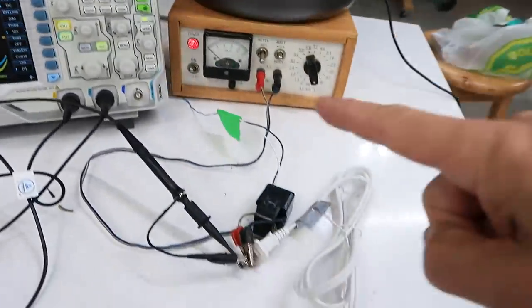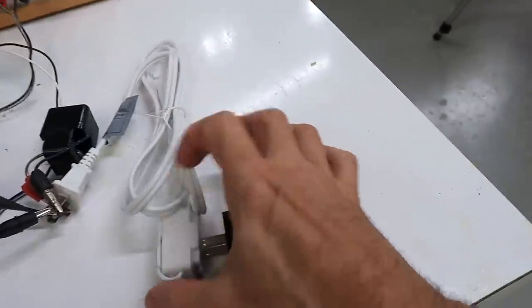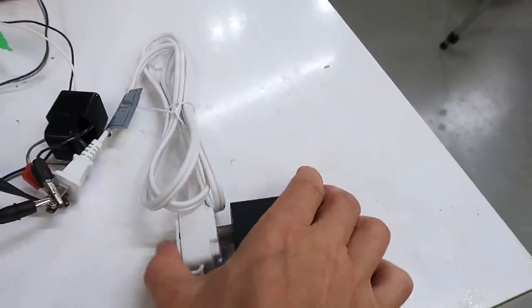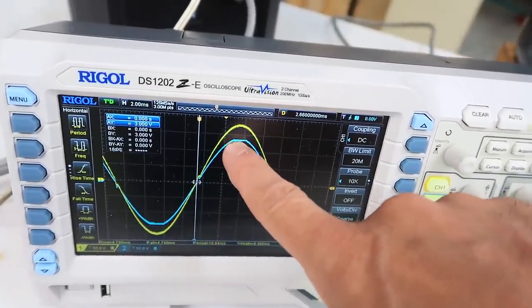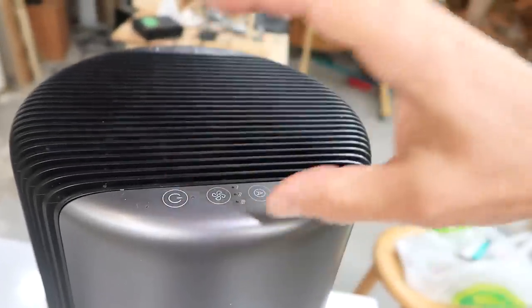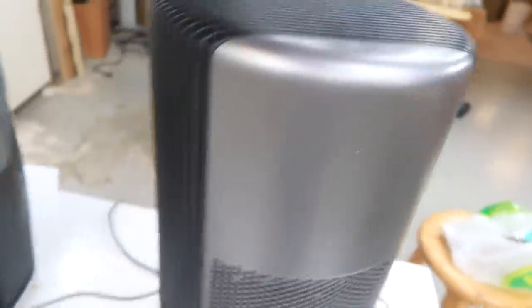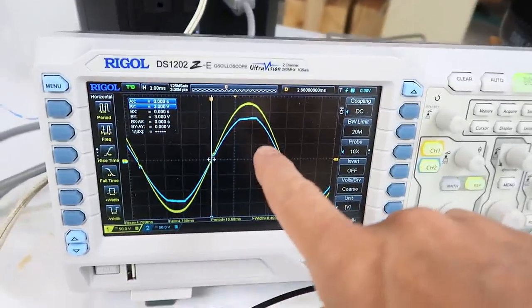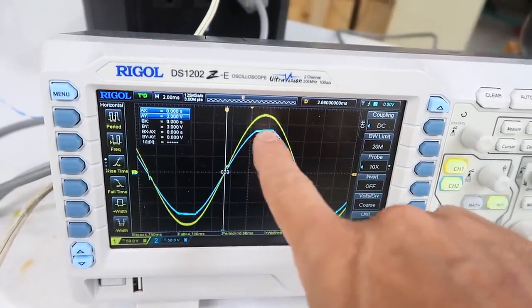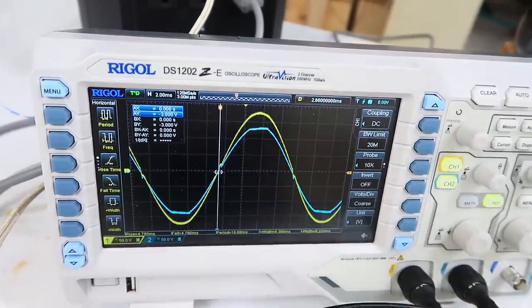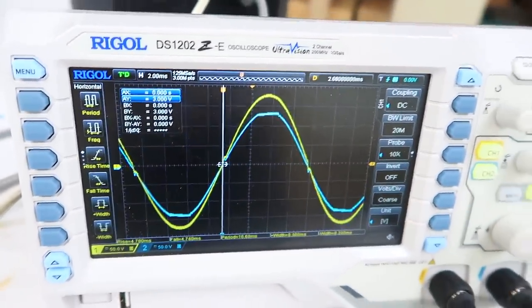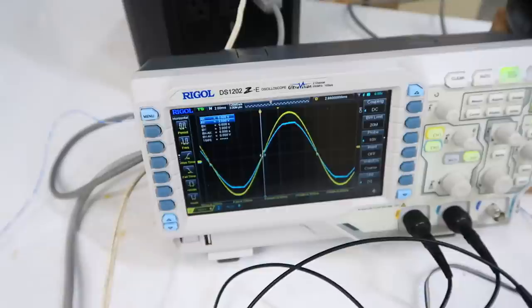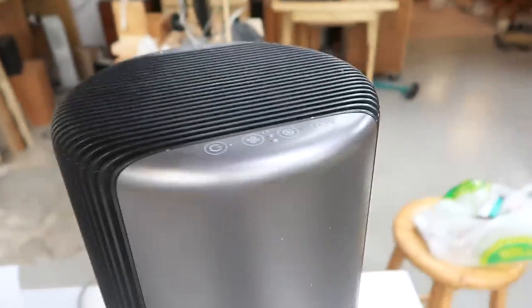But now let's take the waveform from this and plug this adapter in here, which is essentially a switching power supply. And already we can see a slight flat spot on the waveform here. Now let's turn on the load, which is an air purifier, and just set to low. And we can see a very distinct sort of slope flat spot on the top. And that flat spot is actually quite similar to the flat spot I'm seeing on the top of the waveform from the power company. And this thing is only set to low.